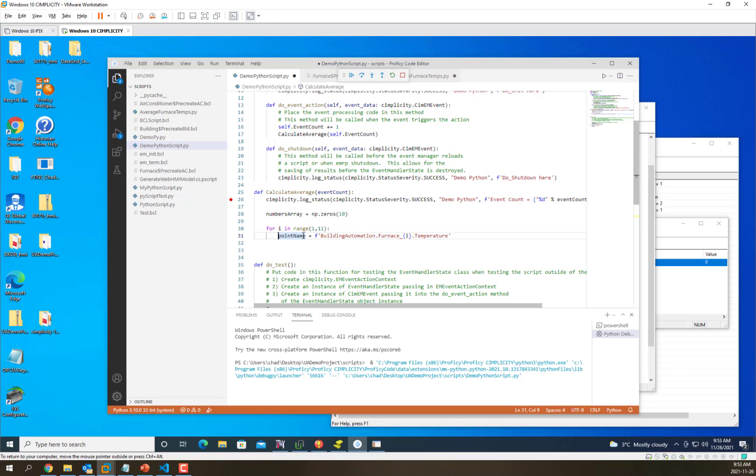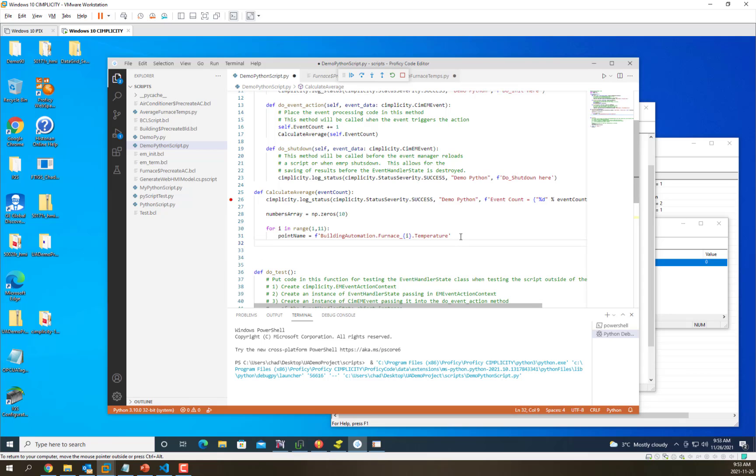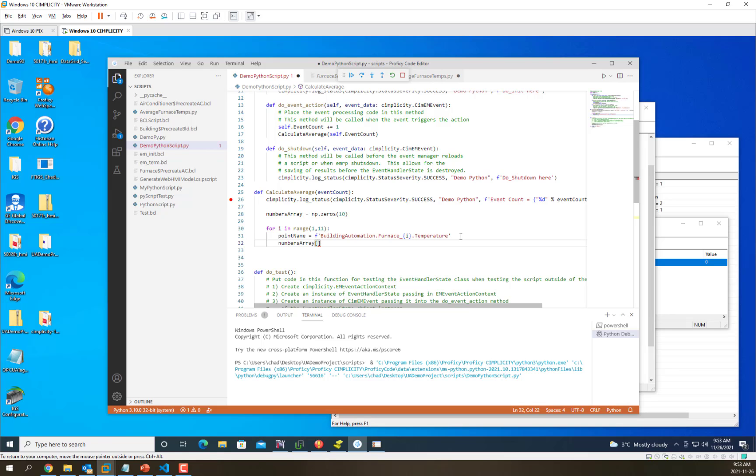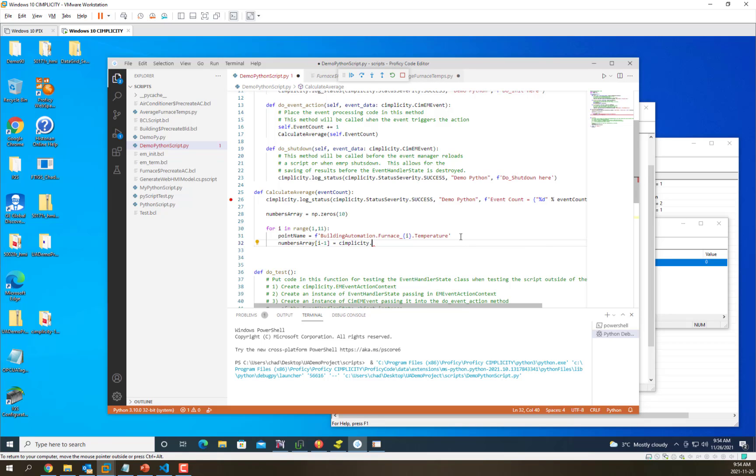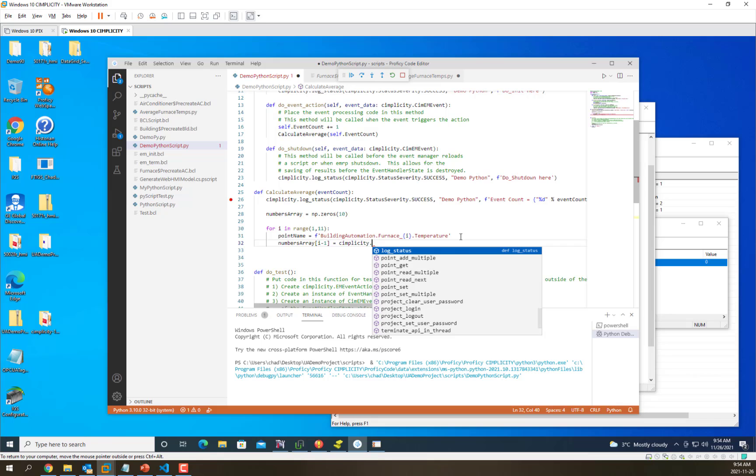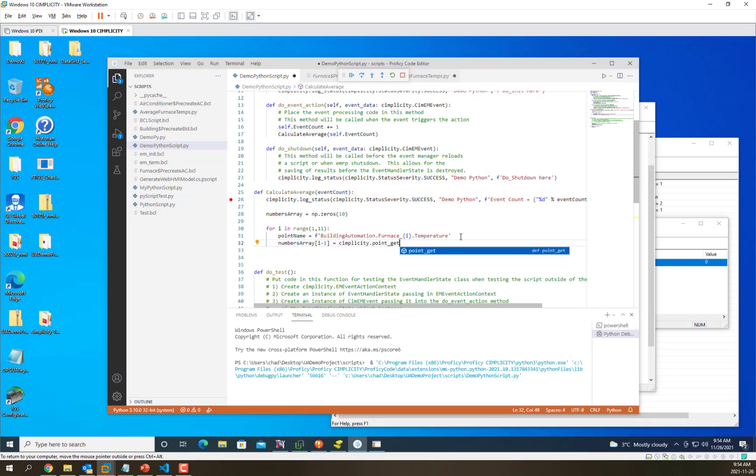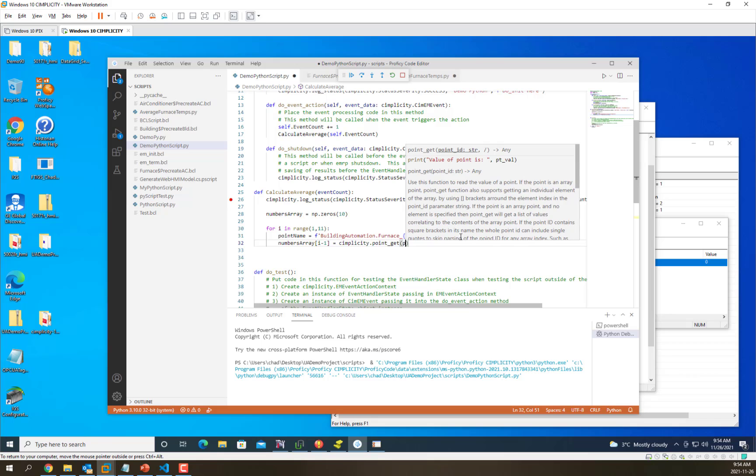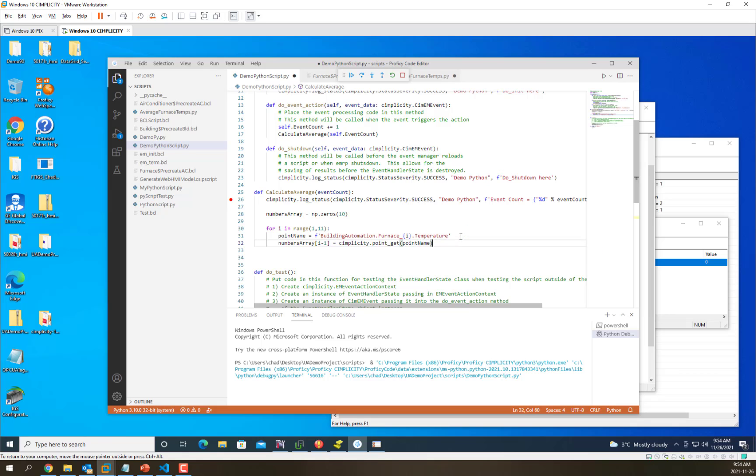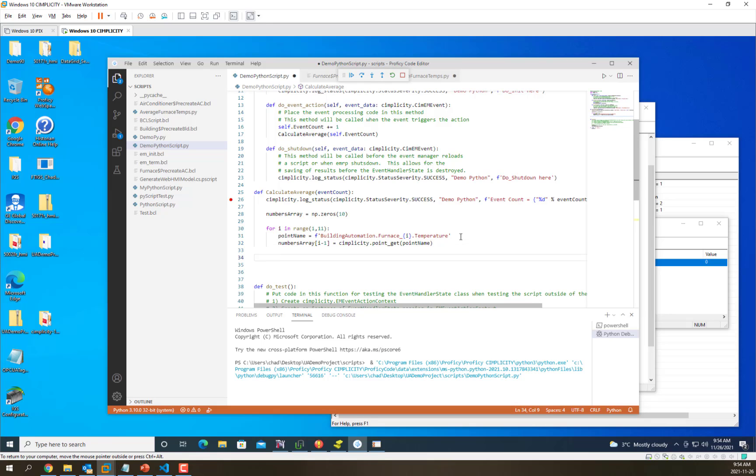We have building automation, furnace, number, temperature. Then we're going to fill in the numbers array. We're going to take i minus 1 because it's zero based. We're going to use the CIMPLICITY library point get function. The point get function takes in the point name, and we're going to fill up that whole array with those values from each one of the furnaces.